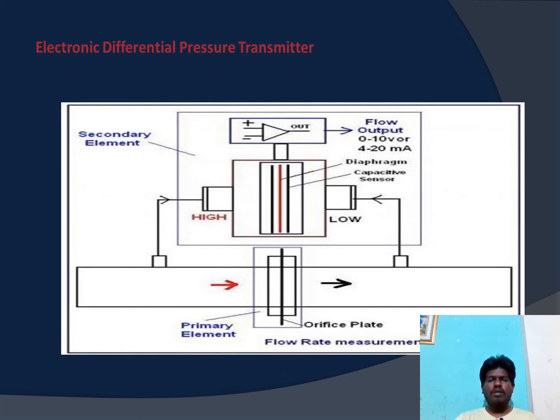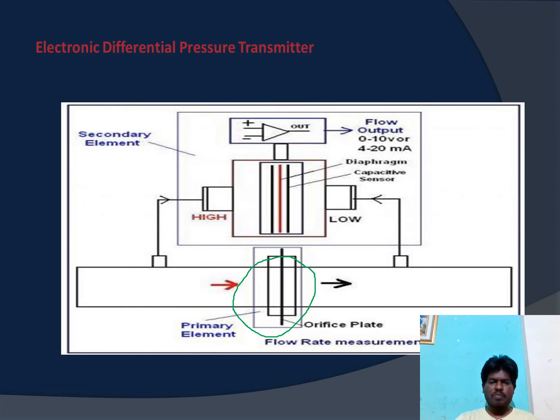This electronic differential pressure transmitter consists of two sensors. The first is a primary sensor, which is located here in a pipeline to generate the differential pressure — it is called an orifice plate. Here we are interested to measure the flow rate through this pipe.